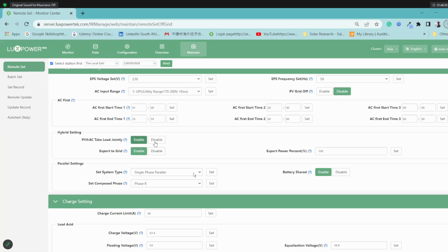It does allow for backfeeding. So you can turn on the hybrid setting and enable the backfeed. There's a client, when I phoned Yaku early on, I tried to get that station for you guys, I can show you. From point of commission, last year end of March, he's backfed a few megawatts of power, which is very nice. So he's almost, well, his system is currently working completely off grid, but he's doing this just to see what the unit's limits are. So yeah, it does work. You can export to the grid, and you can also control the export power percentage.